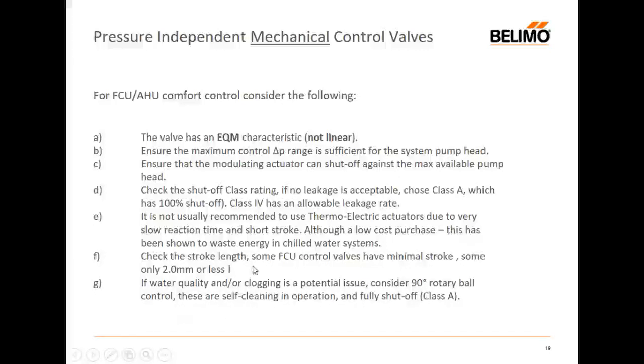So check the stroke length on your control valves, because some have tiny, tiny strokes. Some only 1.5 or 2 millimeters, could be less. And that is not a lot of travel for the 10 volts that's going to come towards the valve in the demand range.